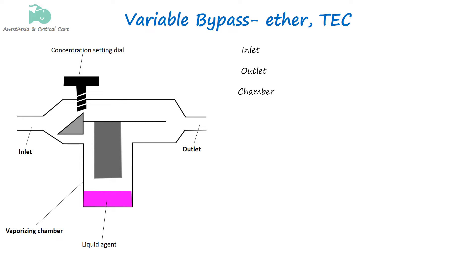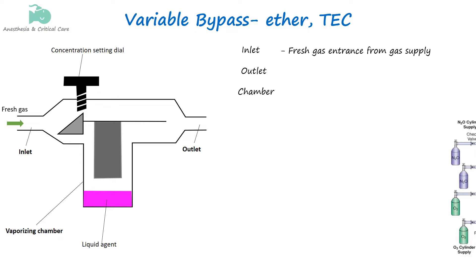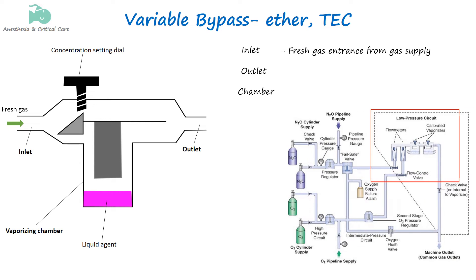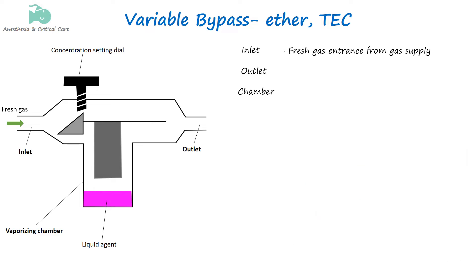Fresh gas enters the vaporizer through the inlet, connecting to a gas supply line, allowing a mixture of gases like oxygen or nitrous oxide to flow into the system. The vaporizing chamber is where liquid anesthetic is converted into vapor.